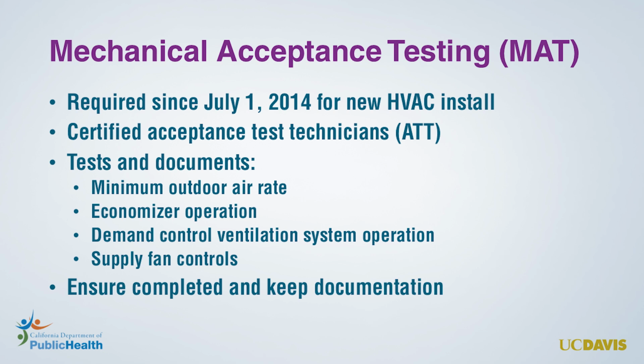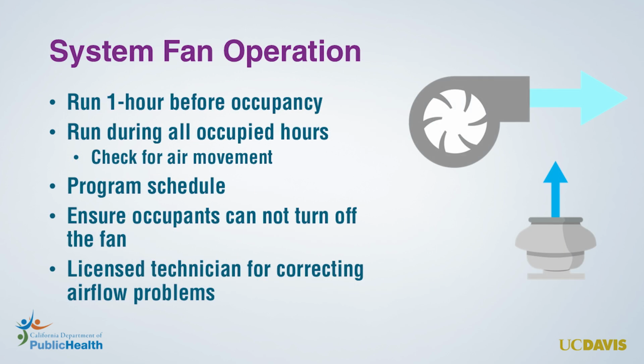An important first step in assessing your HVAC system's health is to confirm whether acceptance testing was conducted during the installation. If this testing was neglected, there's a higher likelihood that your system may currently experience issues stemming from its original installation. There are some basic inspections that maintenance staff can do to evaluate the filtration and ventilation system.